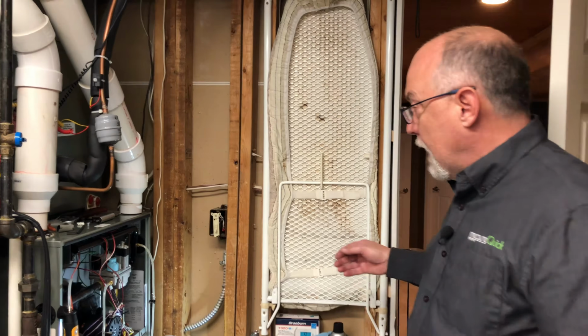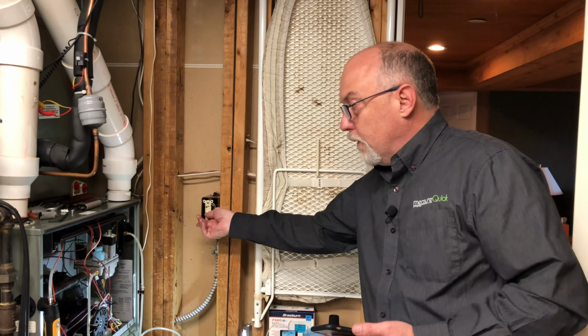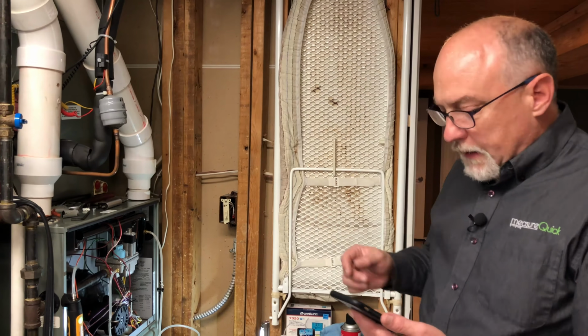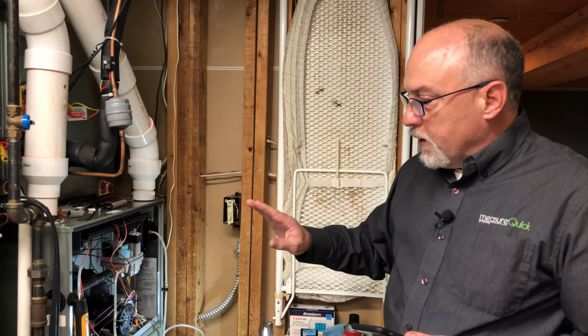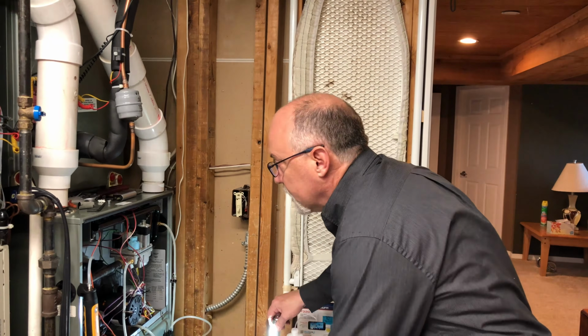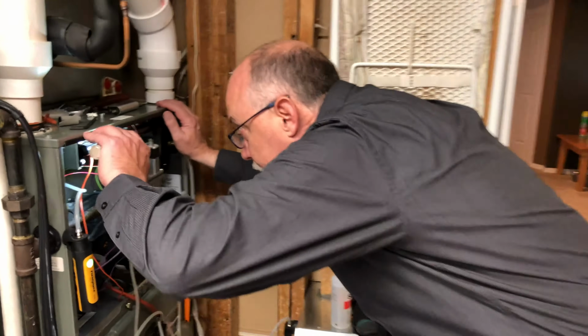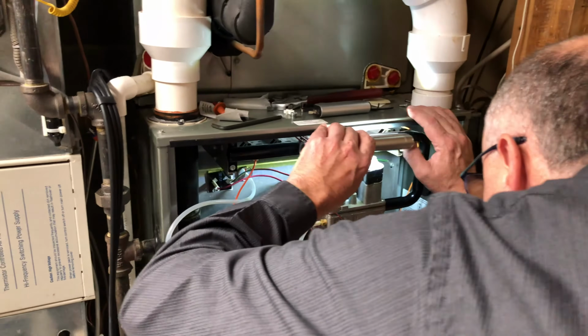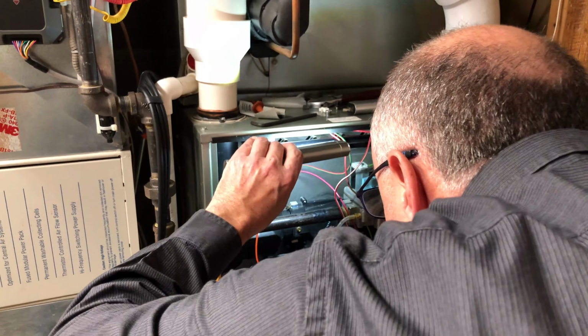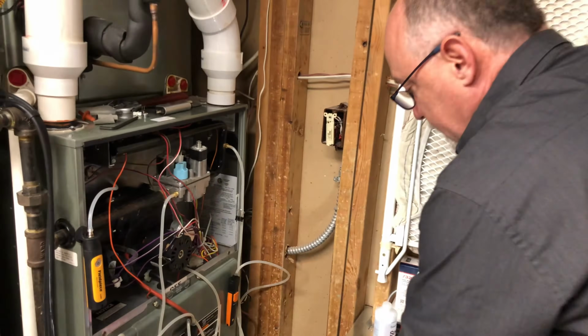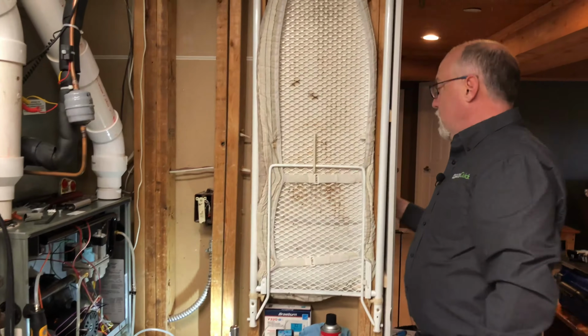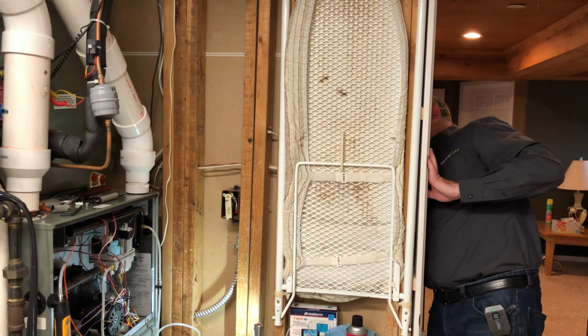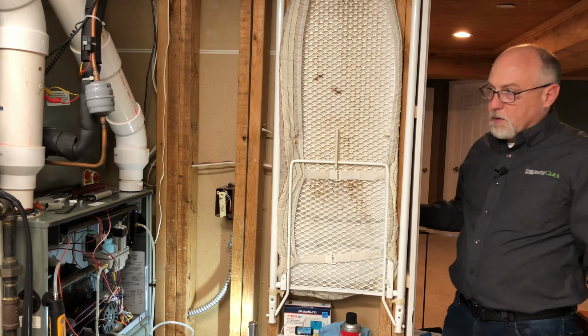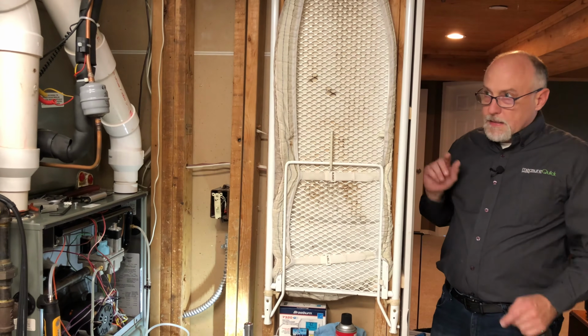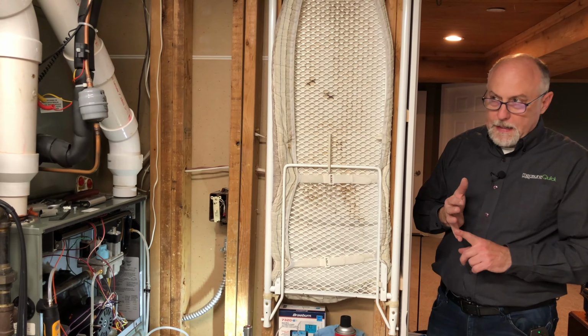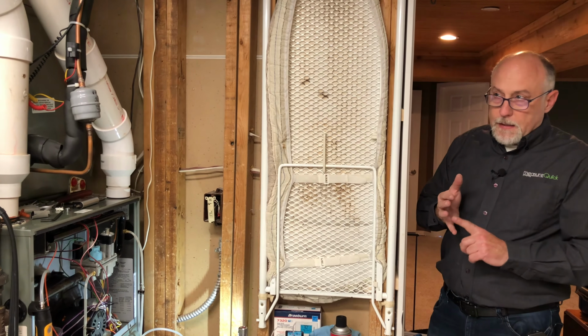Heat exchanger, I'm going to go ahead and we're going to fire the furnace up here, and we're going to take a look at a couple things. On the heat exchanger, the one thing we want to do is, first of all, a basic visual inspection, which I'll just pop my camera up here and see, or my flashlight. You can see there's almost no visibility in this heat exchanger here. So what we really want to watch for is we want to make sure there's no flame disruption when the appliance starts, and we want to do a test for, I've got to wait for my thermostat to wake up here. We've got to do a test in the airstream in the ambient air for CO, the return air, and the supply air for CO.